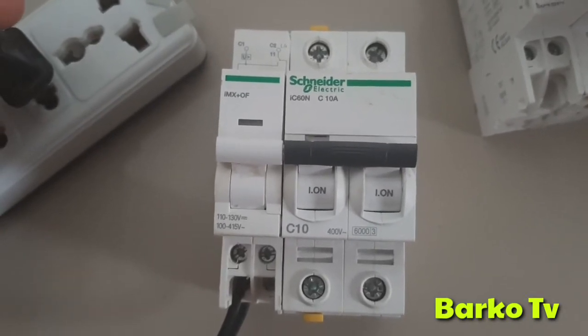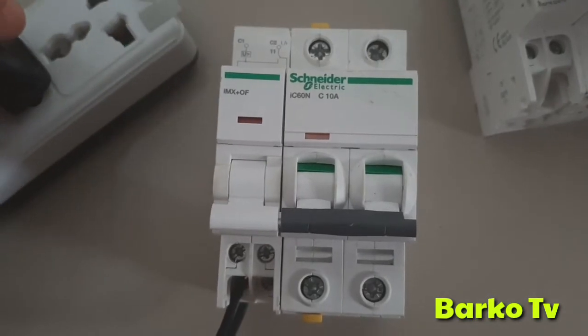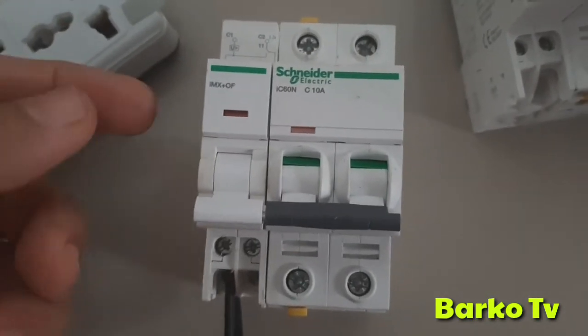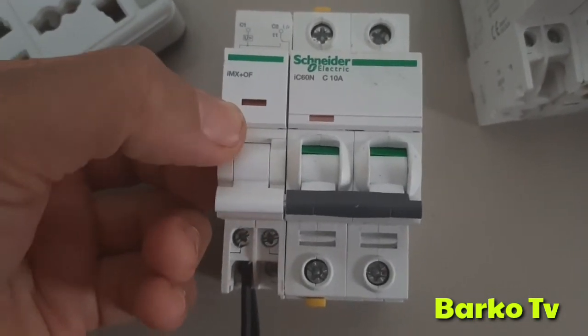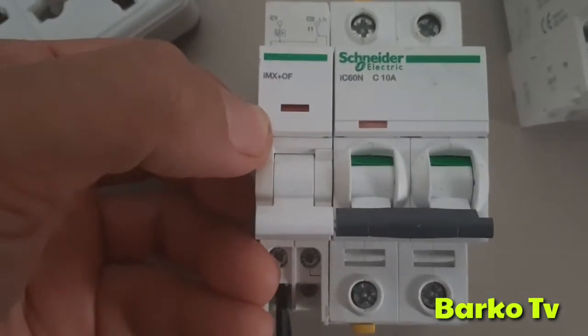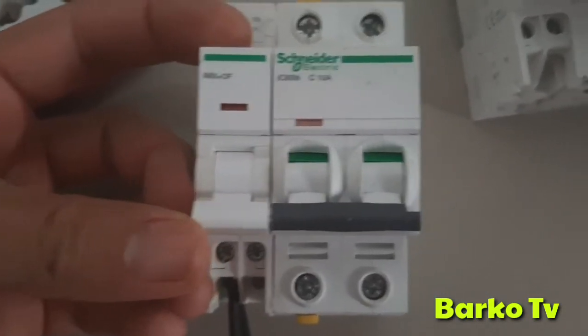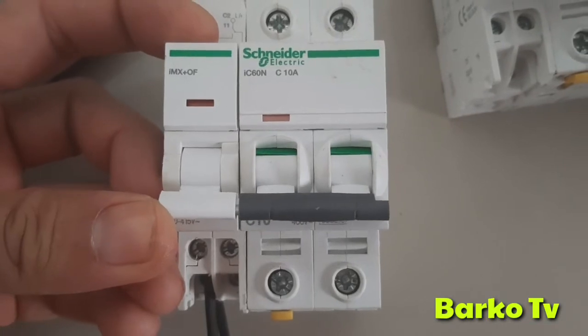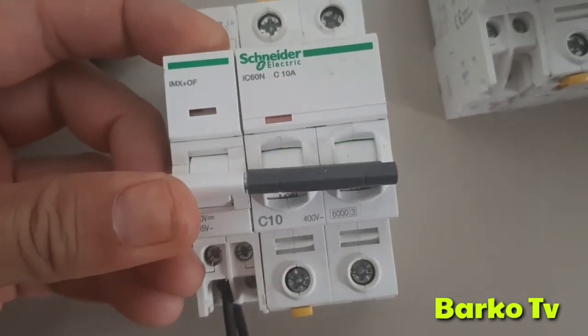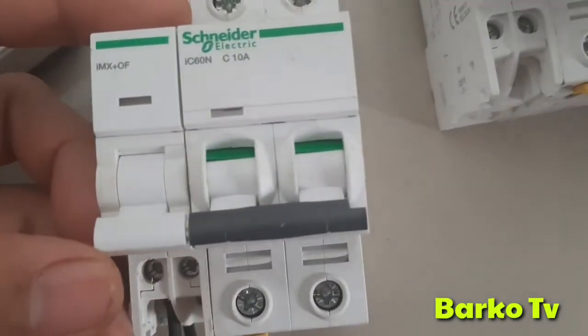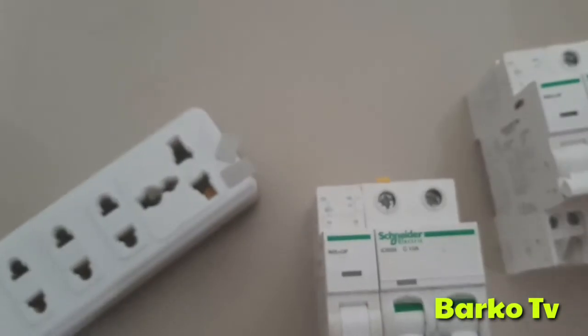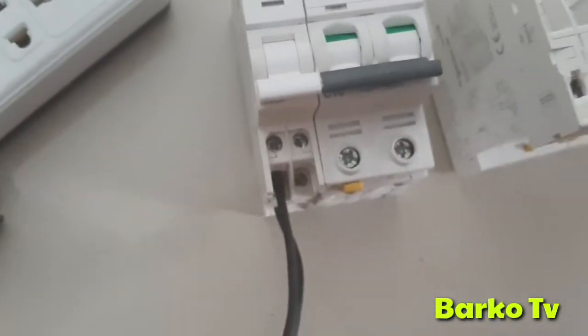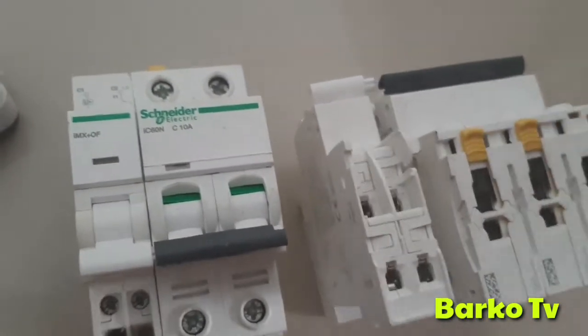Again, I will place a supply. Put a supply. See? This device is activated. The trip term is for the MCB. If it is a short circuit or other trips, it will also change the state. Means the shunt trip device is activated because it changed its indicator color.